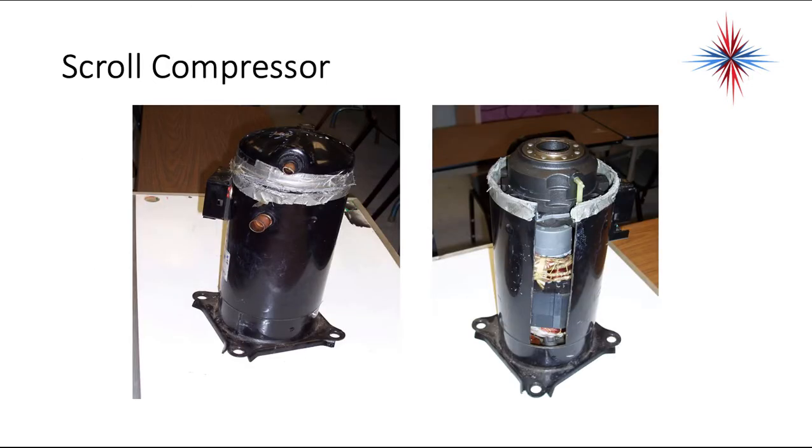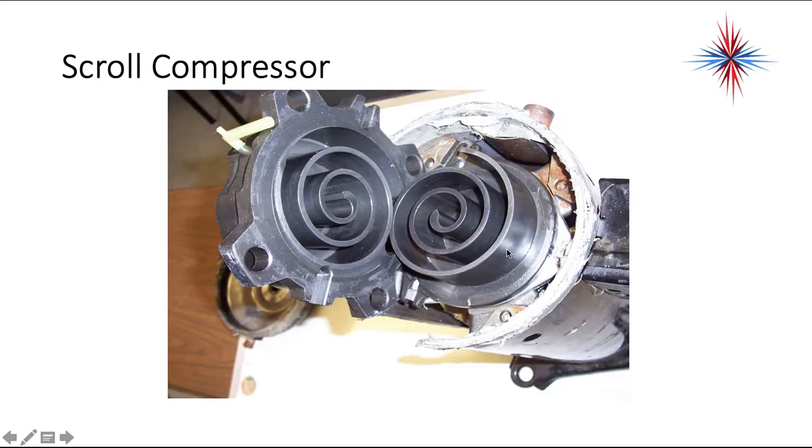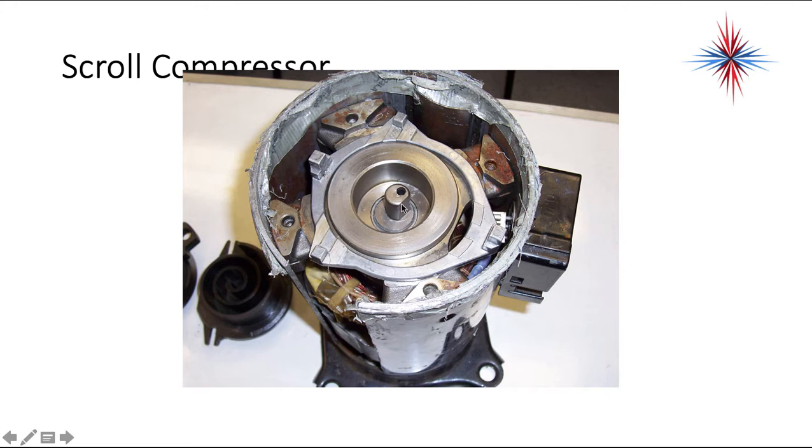Okay, this is taking apart a scroll compressor. We took a saw and a grinder wheel, and we actually cut the scroll apart. So you see the scroll compressor on the left. Now you see how the motor components are down near the base. And as we open up the top, the stationary scroll is up top, and the driven scroll, and you see how they fit together in a scroll pattern. Down here, once you remove the scroll, you can actually see the off-center motor. When this rotates, it's rotating the driven scroll in a sort of offset, since that is not in the center.